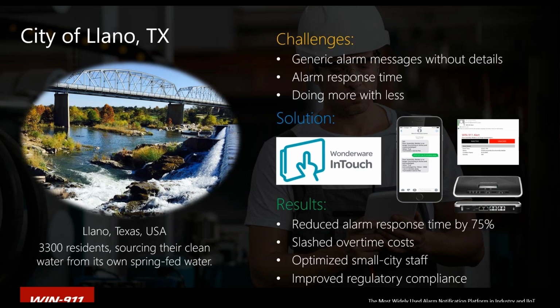In this specific example, they already had Wonderware InTouch installed, but they were looking to meet some challenges, specifically with response times, both when people are in the plant or after hours. The problem was they were just getting a generic message that there was an alarm without much detail, so response times were much slower because they had to get back to the system to understand the problem before they could assess it and make a plan to solve it. So what we were able to do is they implemented WIN-911.